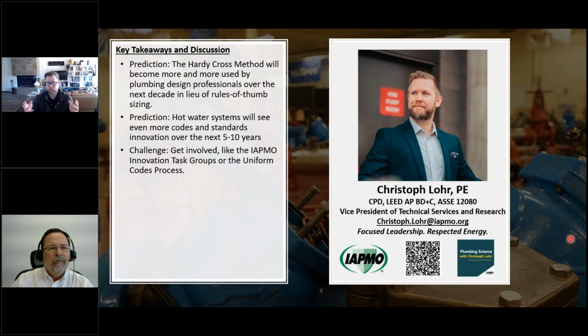your whole hot water recirculation system should always be commissioned. So in the sense, verify that the flows are flowing, that you're getting hot water in each of those loops. So a port could be useful to just knowing and verifying that you get flow upstream and downstream. But really, when you talk about automatic balancing valves, again, pressure independent type, thermostatic, or electronic, none of them have a requirement to be tested and balanced because they're automatically balancing. They're going to do it themselves.